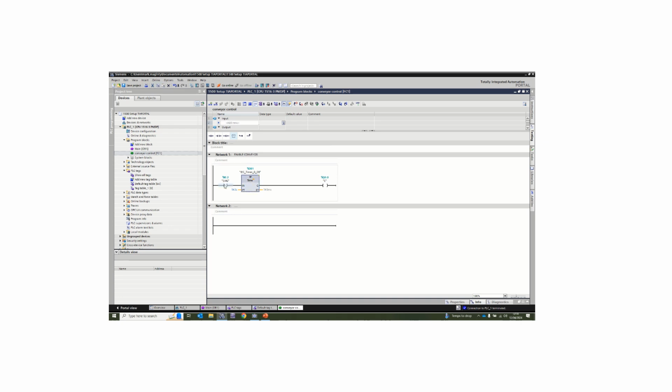So the input to this is going to be SWG. If you get a rise of input into IN, it will then run this pulse timer for 3 seconds, no matter how long SWG was on for. As long as it's picked up within 1 scan cycle or it's held on forever, the output Q, which will drive the E, enable for the conveyor, will be on for PT amount of time, or in our case, 3 seconds. So very simply, in layman's terms, activate SWG, this timer will turn that output on for 3 seconds only. So we'll just download that, we'll make sure everyone's happy with the understanding, and then we'll look at why that may not be the best option as well.